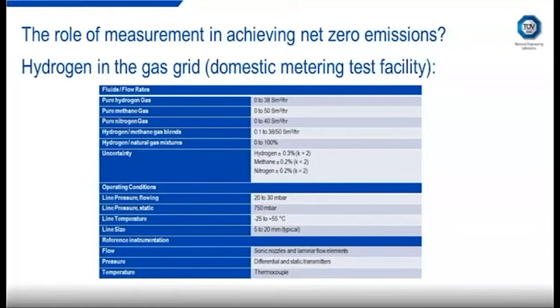So we're expecting temperatures between -25 and +55 degrees. It's a relatively small scale facility, but we expect to be able to test many different types of meter, not just domestic gas meters. In terms of the reference devices that are used, for the flow reference devices, we're mostly using sonic nozzles, but for the very smallest flow rates, we're also using laminar flow elements. But that gives you an overview of the first hydrogen facility that we're intending to build.